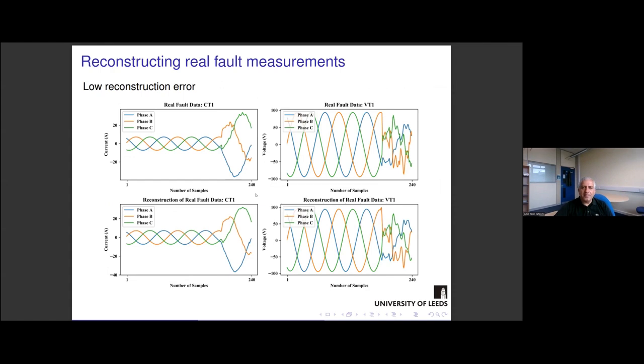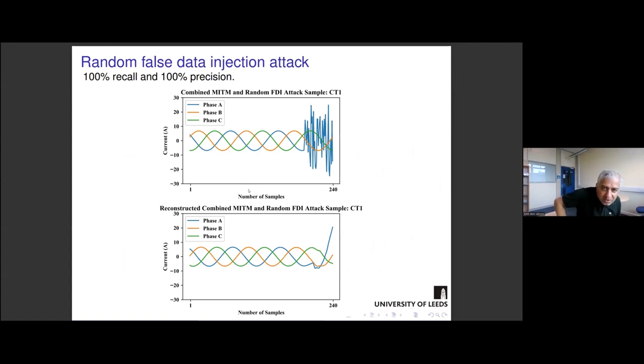Here we can see the reconstruction of real fault measurements in the substation. As we can see, the measurements from the CT and the voltage transformer were reconstructed beautifully using the autoencoder. There is no major difference between the two, and the error level was very low. Then we tested this anomaly detection system for the three types of attack scenarios that I mentioned. We first used random data injection into the process bus. As we can see at the bottom of the slide, the autoencoder was not able to reconstruct the random data, so it was easy to identify this type of attack.